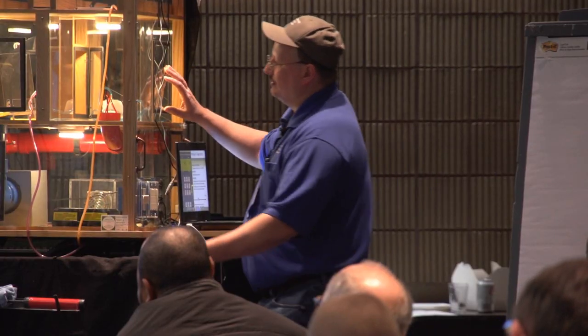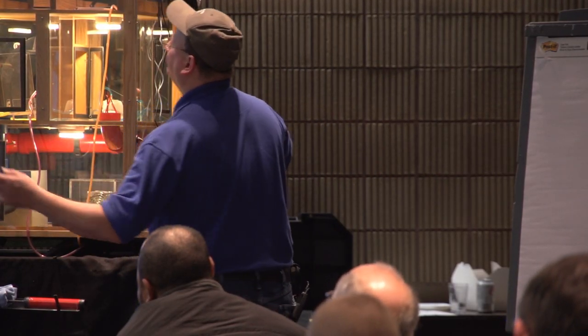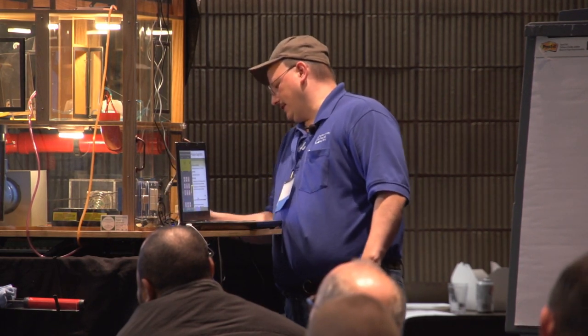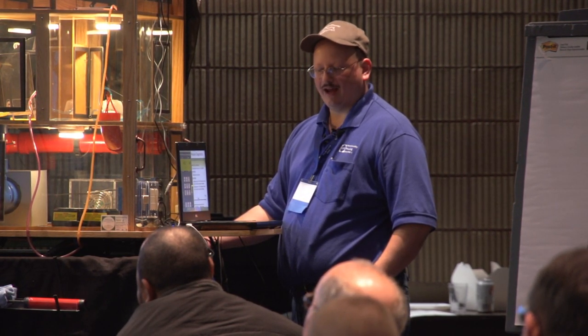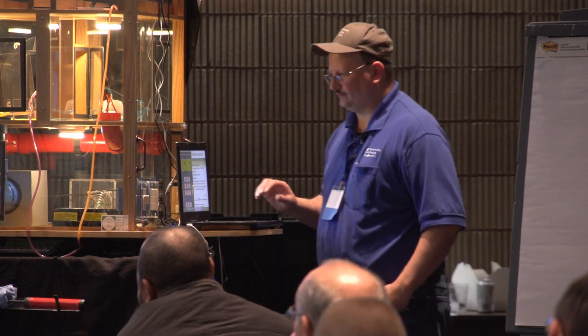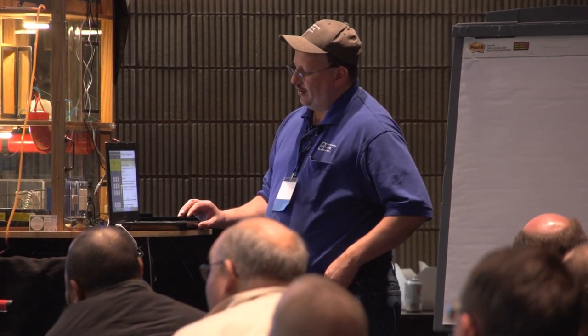I've got all my exterior windows and doors closed and so on. So I'm going to turn that up to 50. Pretty tight house. Get it to 50. That's close enough. All right, if y'all can see my pointer down here at the bottom, that's where my green hose is going outside. That's my 50. This other hose, there's nothing on the bottom port. The top port has this yellow hose on it. Just by looking at this gauge, we can tell we're at 50.